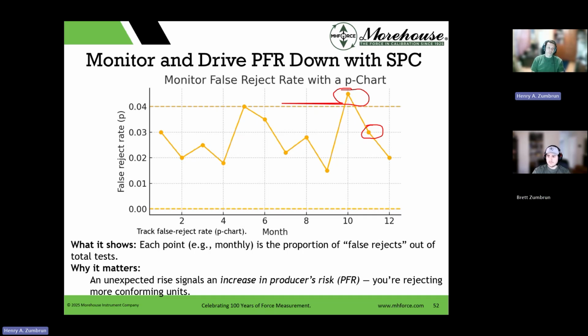The reason that happened was a customer was questioning their data. I went back and said, "Hey, the high range is the lowest it's ever been over the last 10 years, and the low range is the worst it's been, by like two or three standard deviations more. Can you recheck it?" The tech rechecked it, and he said he thinks he had an alignment issue at the time of calibration, and then everything came in. This was before the instrument went out, so we're in that rework phase while it's still cheap and not costly for the customer.